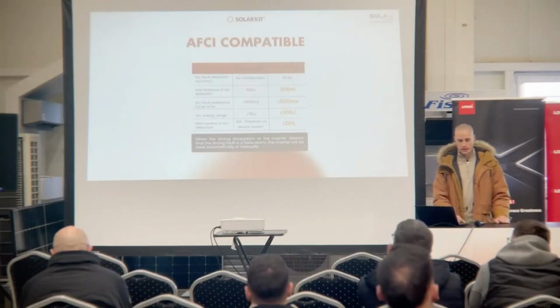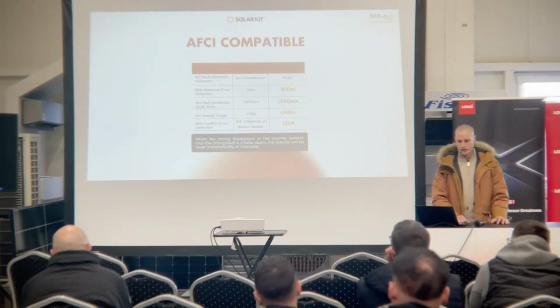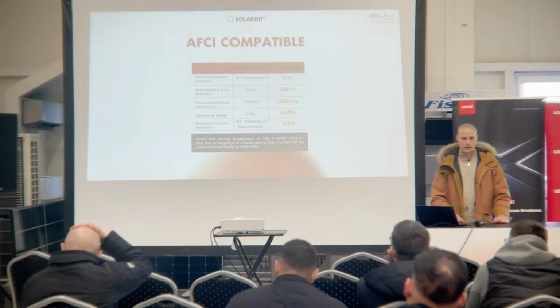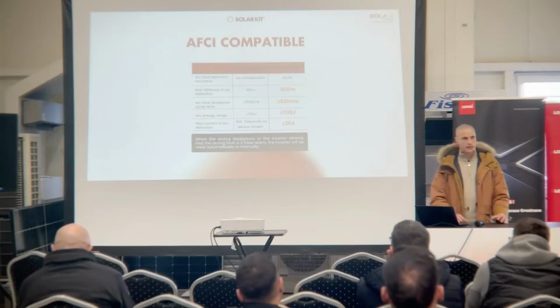Some standards. On the left side, the IEC standard shows what the standard requires. On the right side, you can see the Solax solution that they extended, for example, the AFCI range detection from 100 to 200 meters. And also they reduced the time needed to clear these arc faults on the DC side. So it's really a great advantage in the safety features of the inverter.